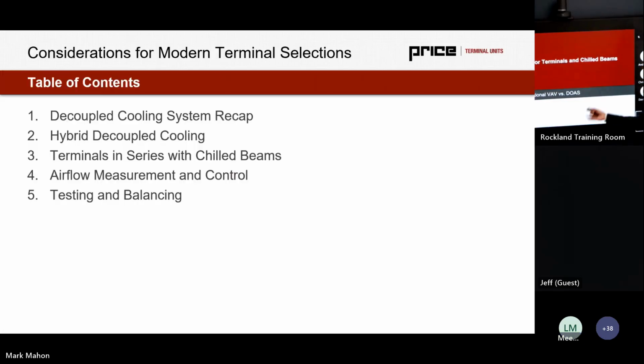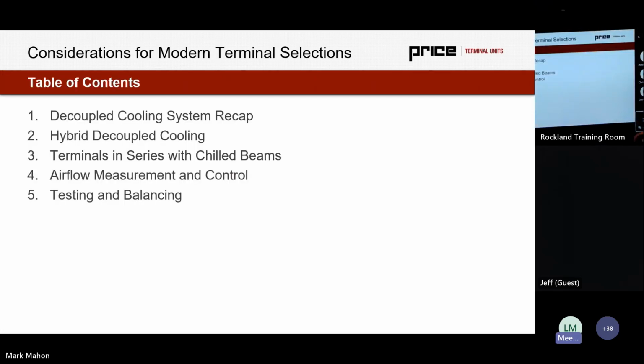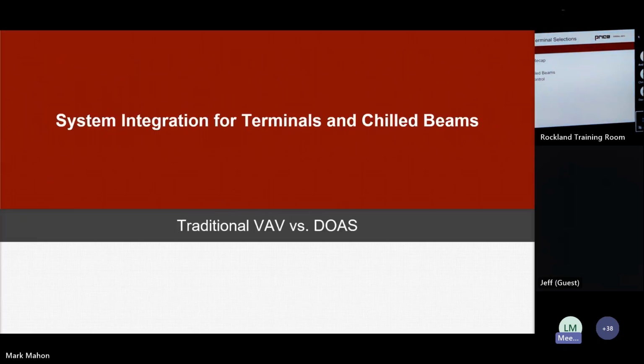So there's a bunch of topics we're going to go through. I do want to do a bit of a decoupled cooling system recap just to refocus us quickly. I have a bit of a different approach to talk about it, maybe some of the rationale in industry, why we see it done more prevalently. Often this is referring to ASHRAE. That's going to be quick. Then I want to talk about a hybrid approach, terminals in series with chilled beams, how they measure and control airflow in a different way, and how testing and balancing them, especially in series with one another, we need to have some additional considerations.